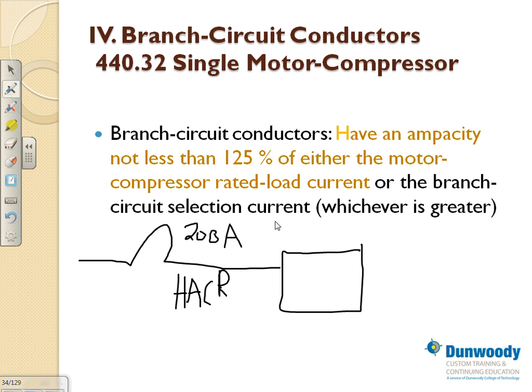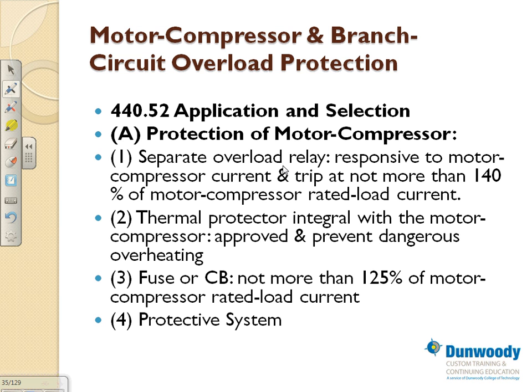When we size the conductor, guys, right here, that conductor, you take it exactly like motors, based on 125% of the compressor rated load current or the branch circuit selection current, whichever is greater. That's the funny thing again about the equipment. They have two values, rated load amps and branch circuit selection amps. Branch circuit selection amps is either equal to the rated or higher. So you choose it, you multiply it.